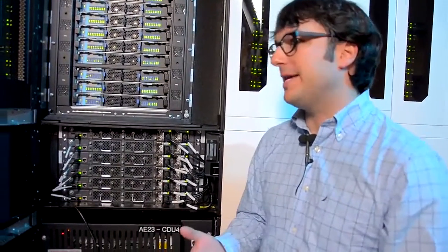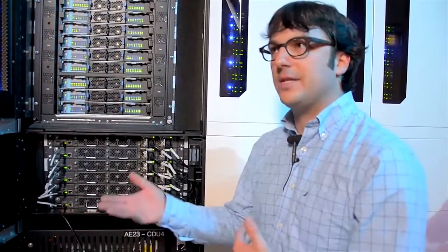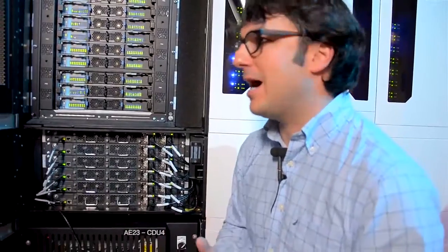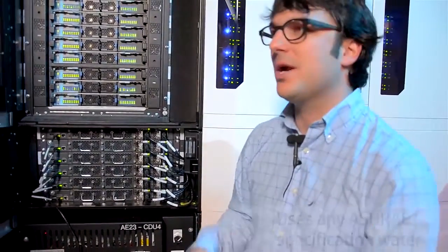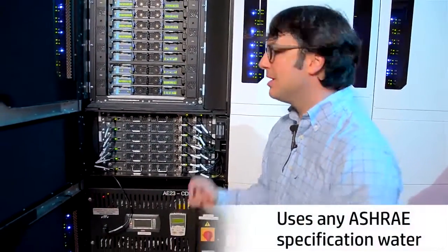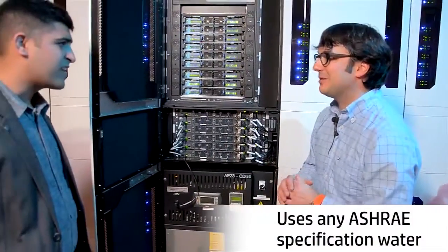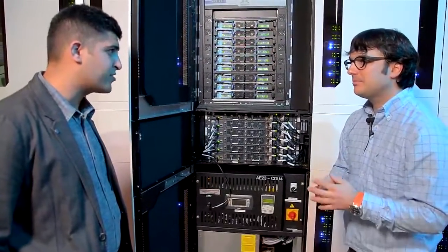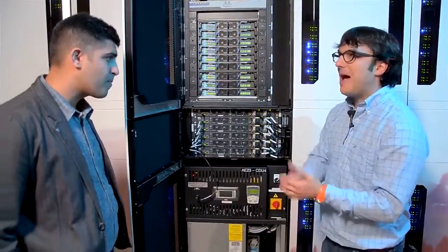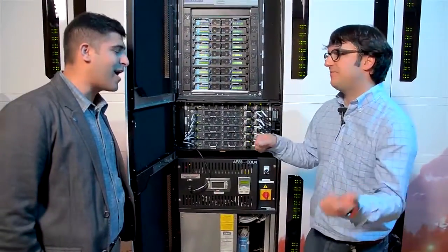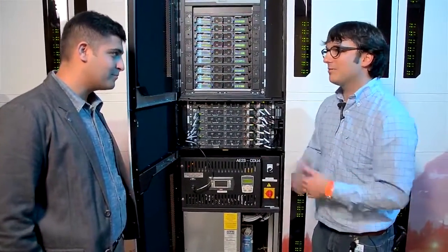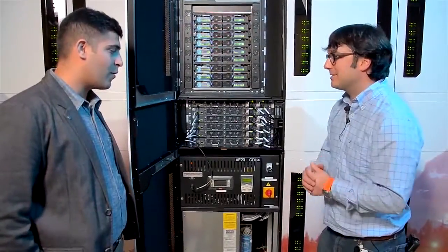Well, water quality aspects and all of those things. Not that we require any exotic water on the secondary side—we don't require deionized water, we don't require distilled water. Basically, any ASHRAE spec water rolls into the system just fine. And is ASHRAE spec water readily available in the data center? Well, here at NREL, their tap water is ASHRAE spec, so we just filled it with a garden hose, and it worked pretty easily.